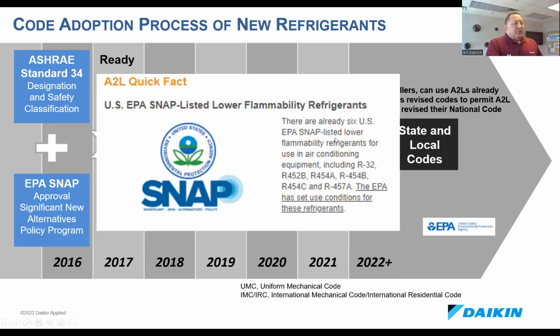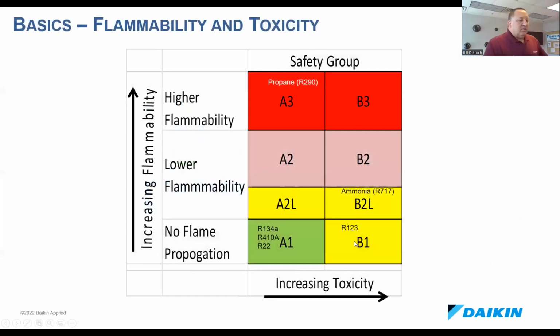And the EPA has already approved a number of these different refrigerants, and these are all pretty much 410A alternatives. So they're lower flammability 2Ls that the EPA has approved for specific applications with specific use restrictions. And if we look at and color code that ASHRAE matrix, you've got your A's and B's, your 1s. I put in some common refrigerants that most people recognize, right?